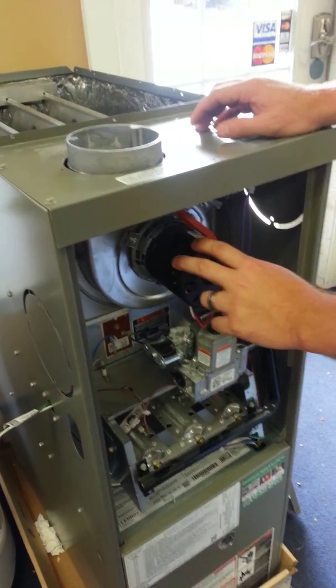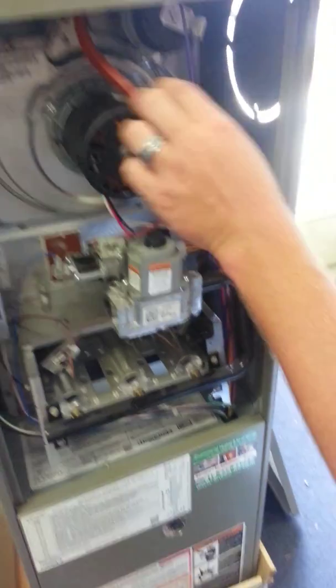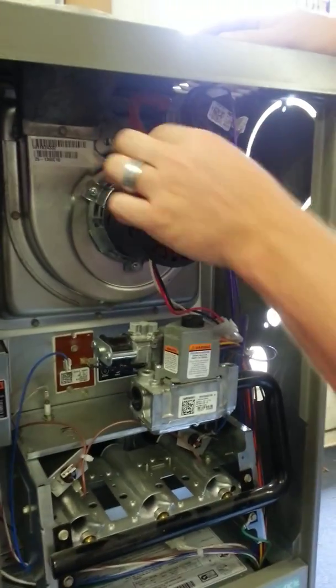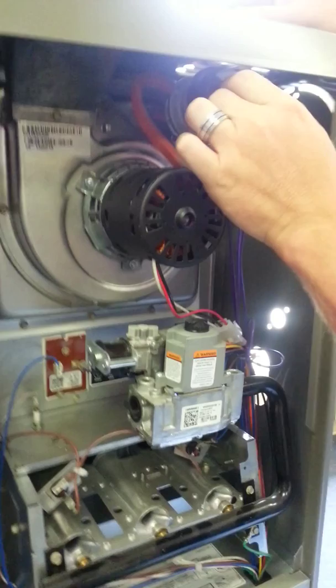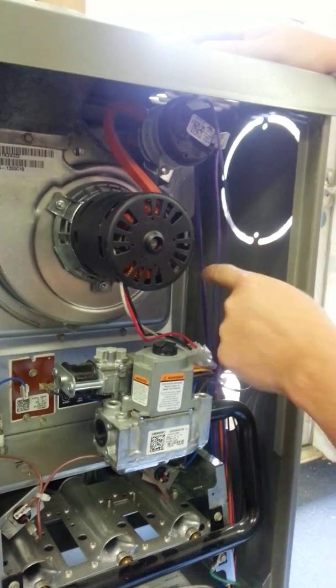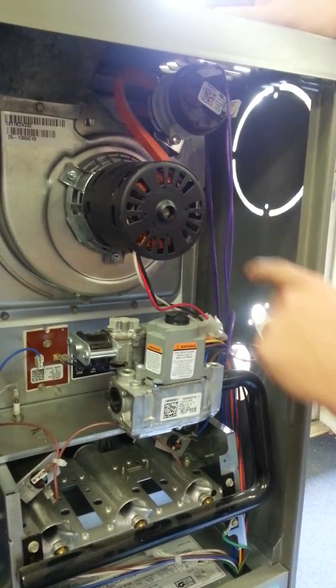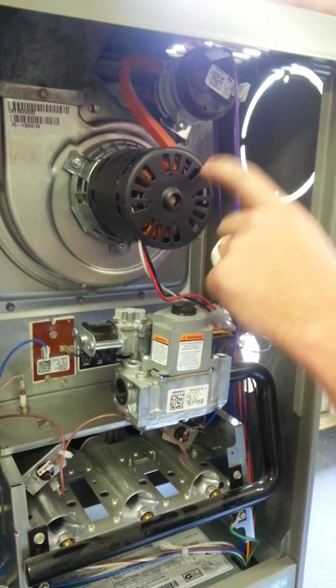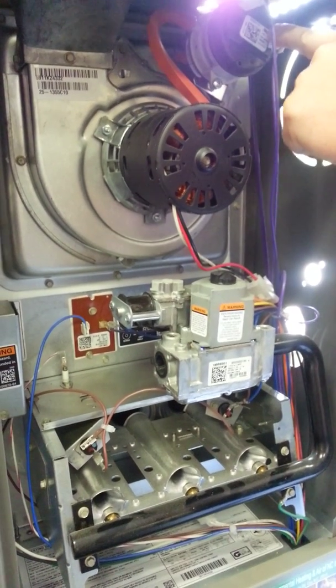Okay, so that's your first level of safety. So once this gets running, there's a barometric pressure switch right here. It pulls a vacuum through this tube, closes these two wires together. This is your control wire from your thermostat. It closes it, says this motor's running, there's no obstructions, you can fire.